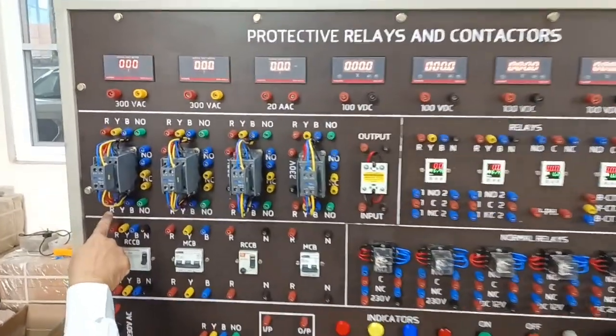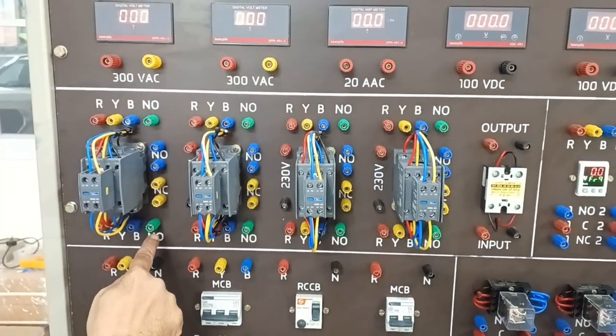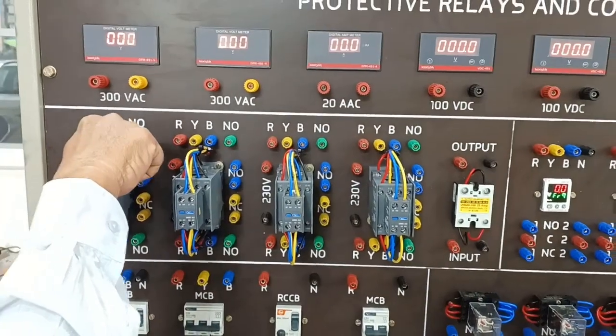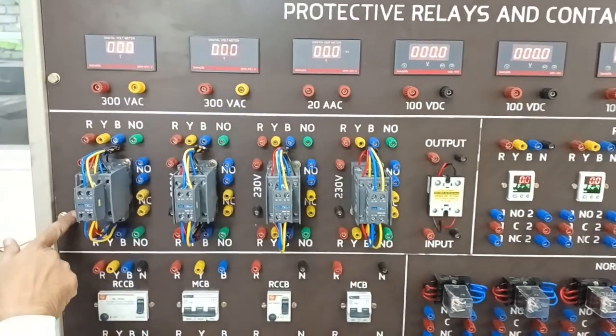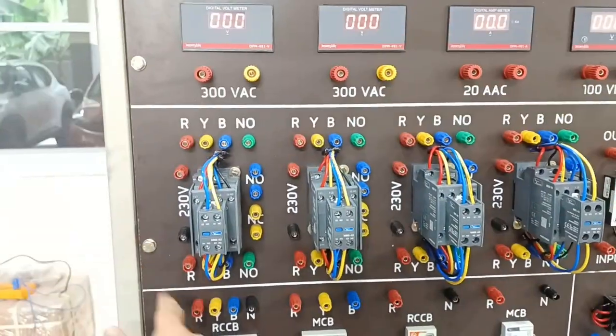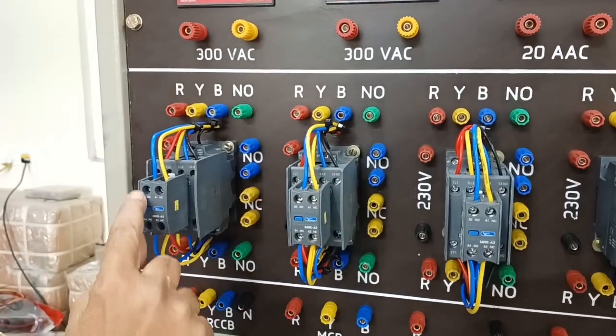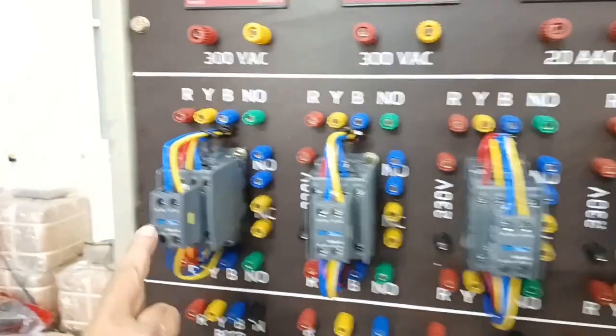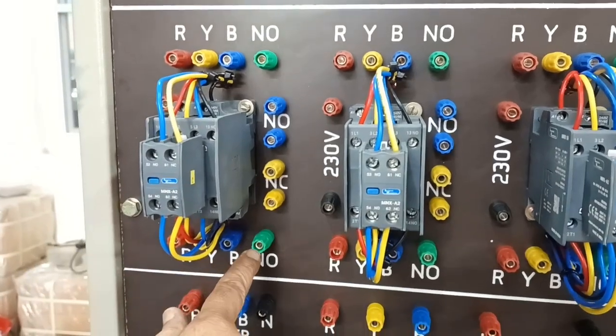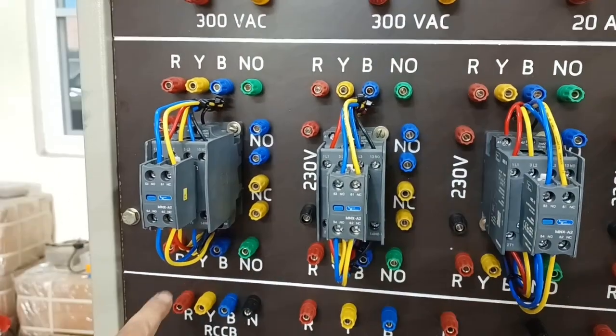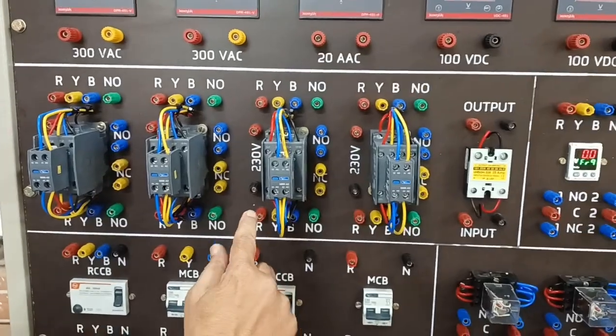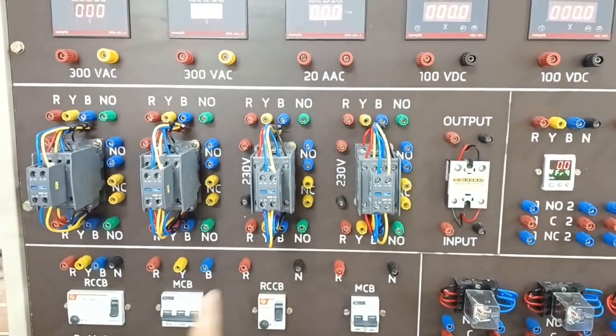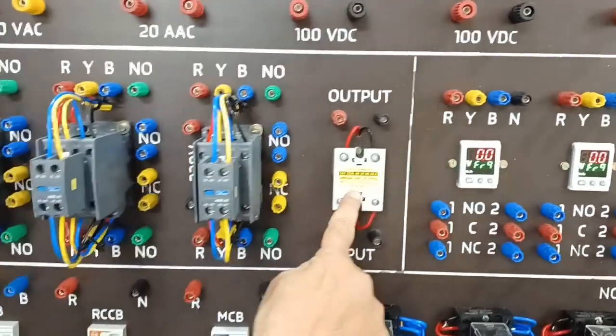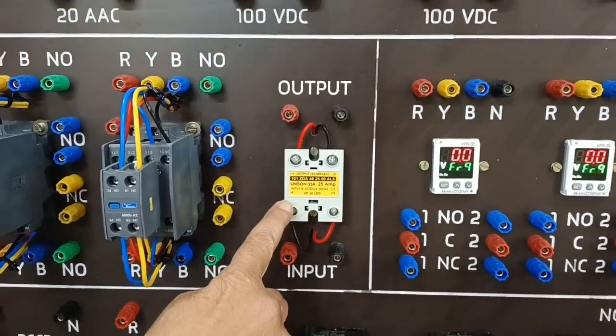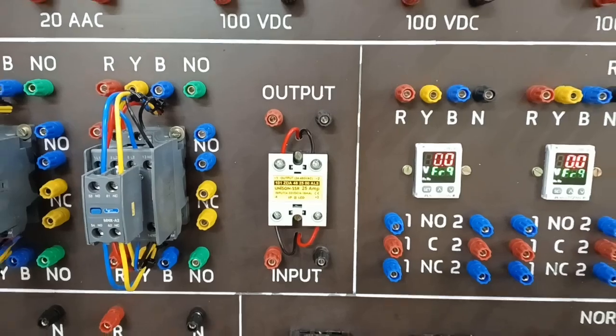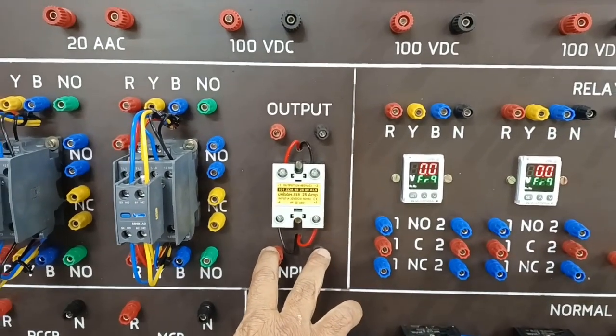This is T1, T2, T3 and NO 1 point, L1, L2, L3 and NO point. And this is auxiliary coil voltage 230 and this is NC NO of a contactor. Say if you want to use this contactor externally, you need to use these terminations for operation. Like this, we have given 4 contactors of the same current rating, 18 amps. Simultaneously, we have given another SSR relay of 25 amps and this will operate from 4 to 32 volts. This is 4 to 32 volts input and this is your contact.